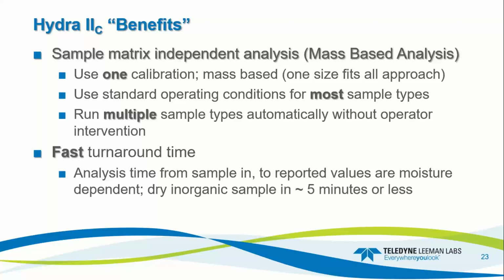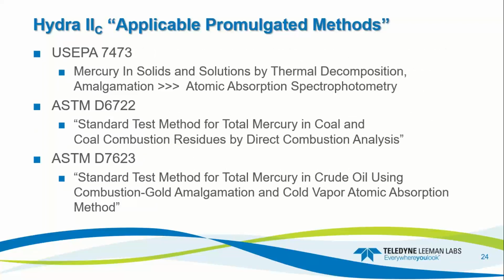Fast turnaround time. Analysis from sample in to reported values are moisture dependent. For dry inorganic samples such as fly ash or samples like that, dry coal, it's going to be approximately 5 minutes or less. Actually, it's probably around 4 minutes to 4 minutes and 10 seconds, thereabouts.